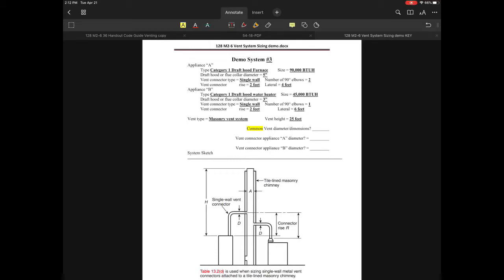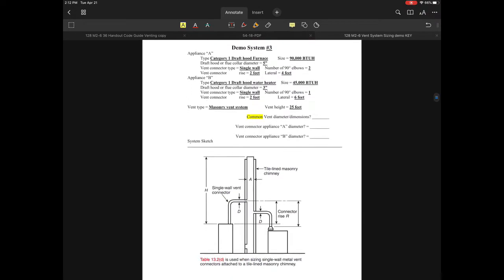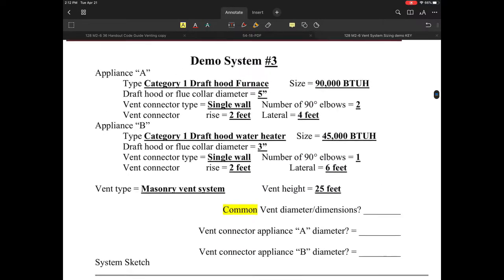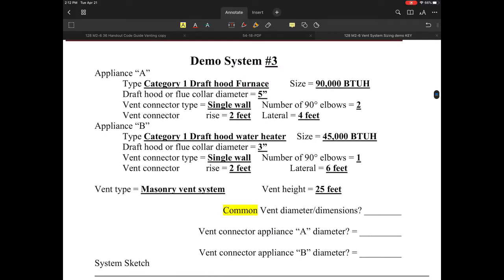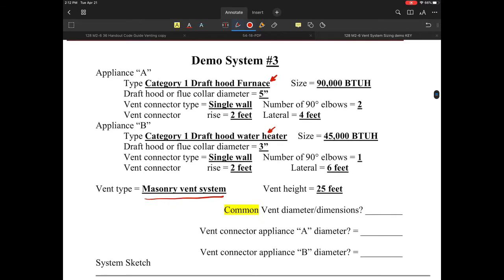Let's take a look at my demo system number three. We have two appliances that we're going to be venting. They are both draft hood type appliances — this one is a draft hood furnace — and we are going to be venting in a common vent chimney. This one happens to be a masonry chimney, common vented with two appliances.